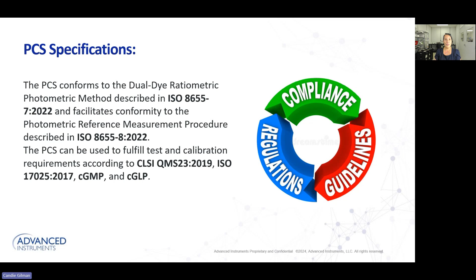All right, so now let's talk a little bit about the regulatory piece. When we think about the PCS system, I mentioned that dual dye ratiometric photometric method. And that method is described in ISO 8655 Part 7. It's also described in the photometric reference measurement procedure that's described in ISO 8655 Part 8. And for PCS customers that are on the clinical side, the system can also fulfill test and calibration requirements according to CLSI QMS 23. If you're an accredited 17025 laboratory, or maybe you're a GMP or GLP facility, our system is housed in all of those different facility types and is used for pipette calibration, as well as operator assessment, interim pipette verification, all of those different tasks and functions.